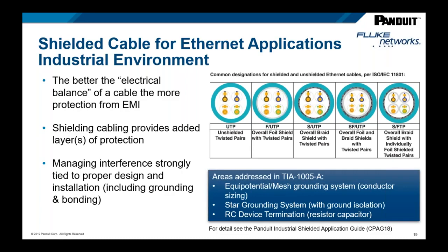Things to consider around shielding and noise: first, determine the source of the noise — is it within the cable or outside the cable, and how is it being brought to the control panel? Then consider the design of the grounding and bonding system. We have to understand both of those things before we can get to product selection. What we always recommend is to first look at the electrical balance of the cable, whether shielded or unshielded.